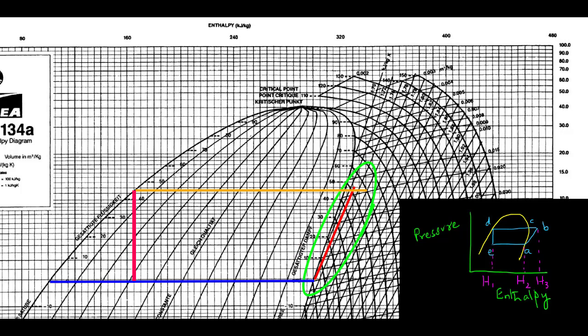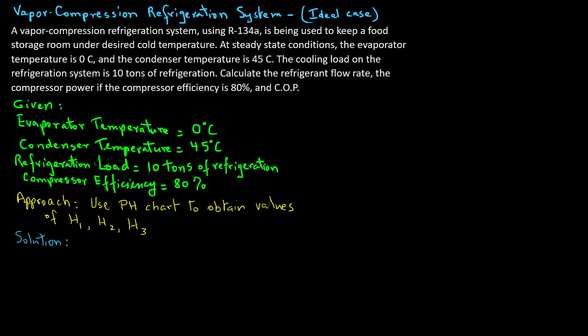On the right-hand side at the saturated vapor curve, we draw the line from A to B in the superheated vapor zone, following one of the constant entropy curves that originates at point A and meets the condenser line to identify point B. With the cycle drawn on the refrigerant chart, we can read the values: H1 equals 164 kJ/kg, H2 equals 299 kJ/kg, and H3 equals 328 kJ/kg.